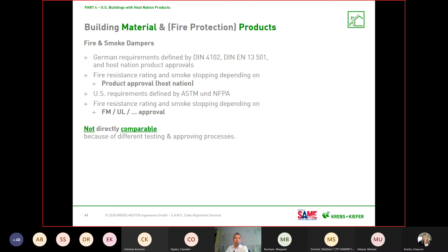You can find a 1.5 hour fire damper tested by UL, but it's not the same as a 90-minute host nation German fire and smoke damper. They're different in design, they're different in testing. So this is the reason why the aligned design should always show the host nation fire protection requirements, the fire ratings, so you're able to choose an appropriate product, door or fire damper, to build it, the fire damper with the correct fire resistance rating and the correct wall.